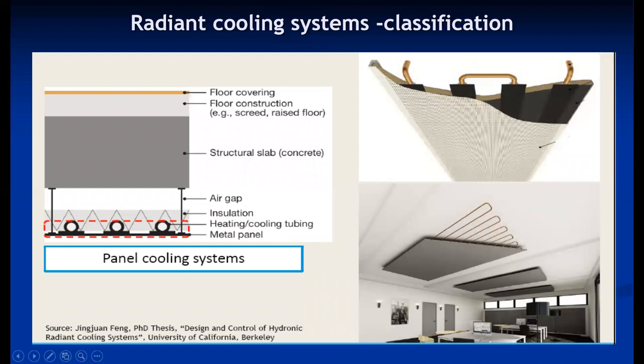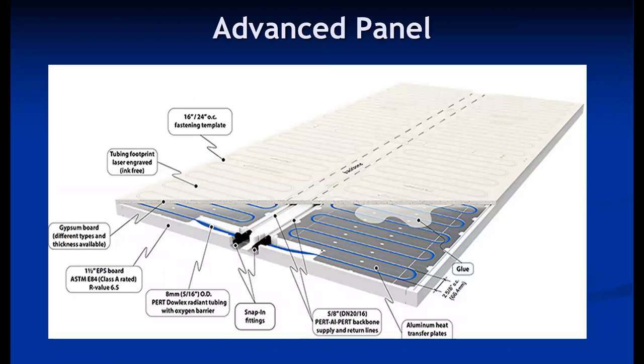The second type is the panel cooling system using separate panels. This system can be used in existing buildings as well. Such panels, embedded with piping, can be easily mounted on the ceiling or floor. This particular structure consists of an air gap, followed by insulation, then heating or cooling tubes, followed by a metal panel — making it flexible and applicable even to existing buildings.